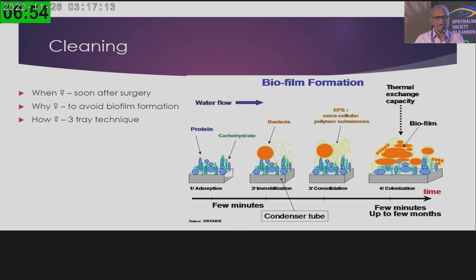When should we clean instruments after surgery? In most OTs, all instruments from about 10 cases are left and cleaned at the end of the surgical session — that is not proper. Instruments must be cleaned immediately after surgery to avoid biofilm formation. If you can clean the instrument within minutes in the earliest stages of biofilm formation, you can get rid of the organisms.